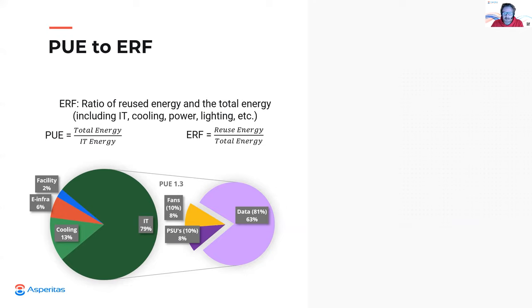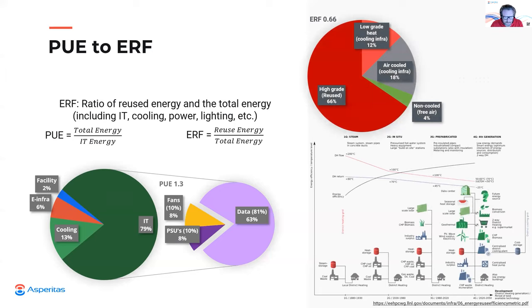This is often mentioned as a reason for hyperscale facilities to be averse to these principles. If a facility has reached its economically achievable efficiency, the PUE metric should simply be abandoned and other KPIs should take over. An example of such a KPI is ERF, or energy reuse factor. ERF indicates how much of the electrical energy is actually converted and delivered as usable heat. This means that the same energy which is used for the IT equipment is given a second life for a completely different process.